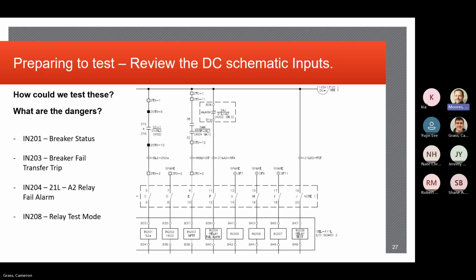In some cases, you're going to have to set up a test plan with your relay. For example, the breaker failure testing I mentioned last week. It uses status of the breaker, it uses current, and it uses a breaker fail initiate from an outside relay. It has to have all of those things, and they have to operate within a certain number of milliseconds. That's a test that we would have to perform. So you'd have to hook up a relay output of the test set to the two inputs of the relay, and the output of the relay to an input of the test set, set up a plan and make all that work, and then test the timing of it all and make sure it only works based on that breaker failure logic.